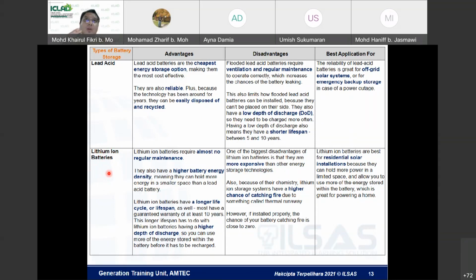This battery is normally used for small scale applications. So if you want to develop a system for BESS to couple with your existing solar system, this is the best battery to choose, because it requires almost no regular maintenance, has higher battery energy density, longer lifespan, and higher depth of discharge (DOD). But the disadvantage is it's more expensive.